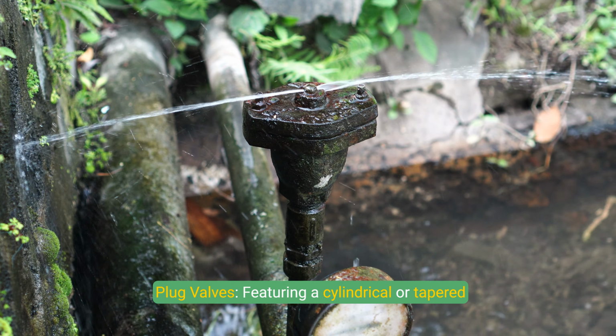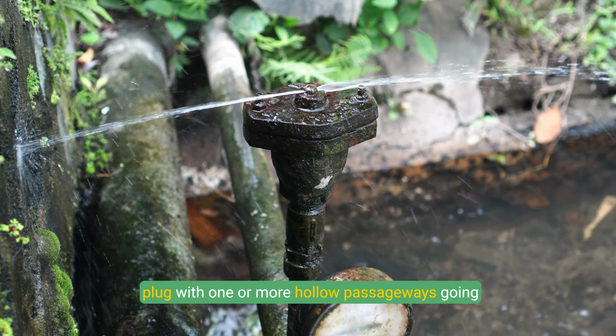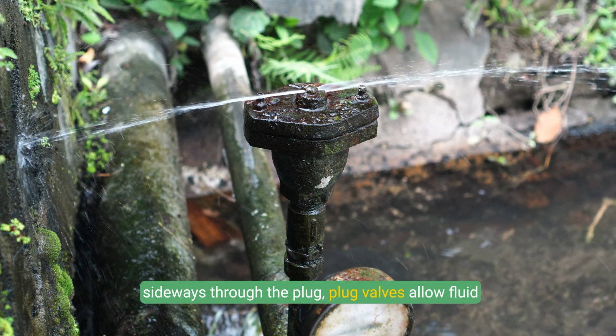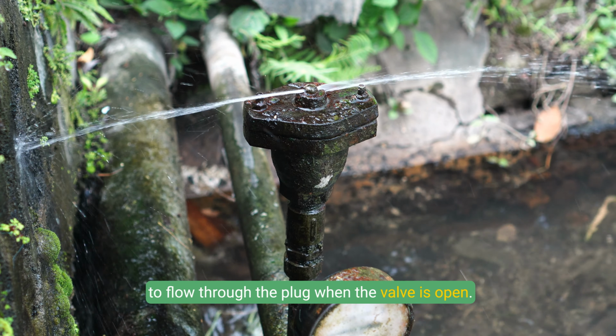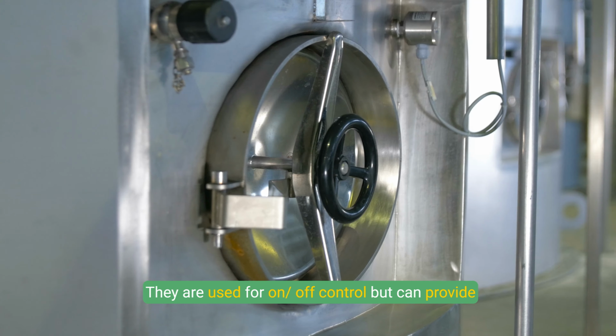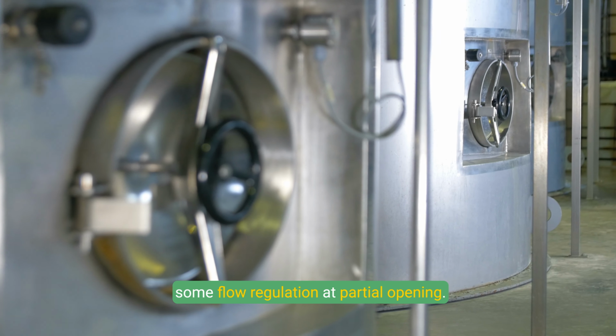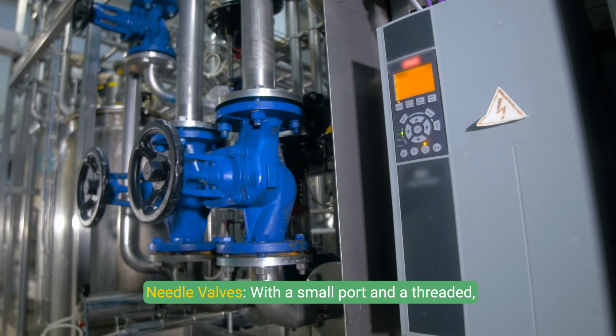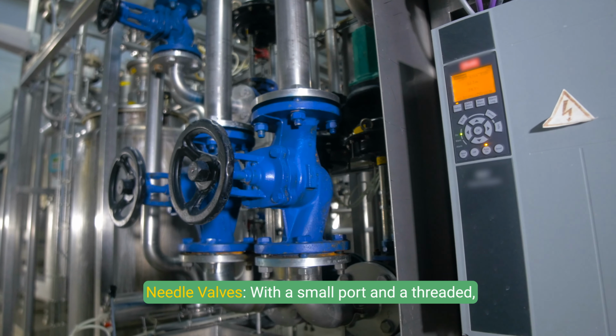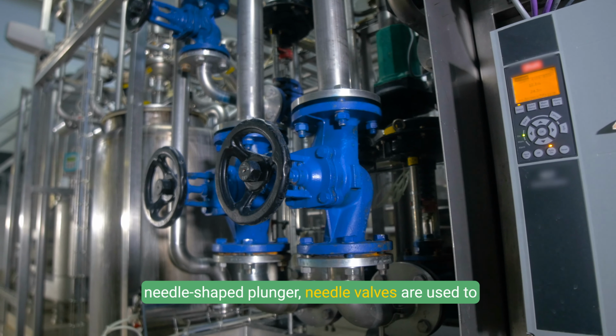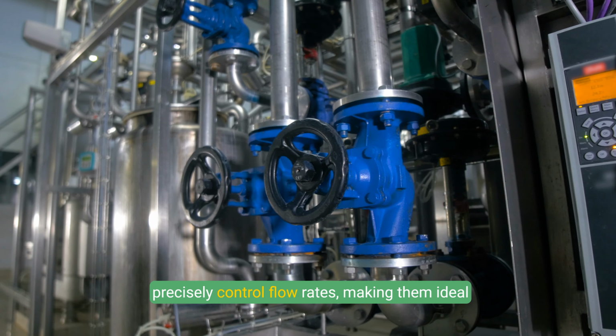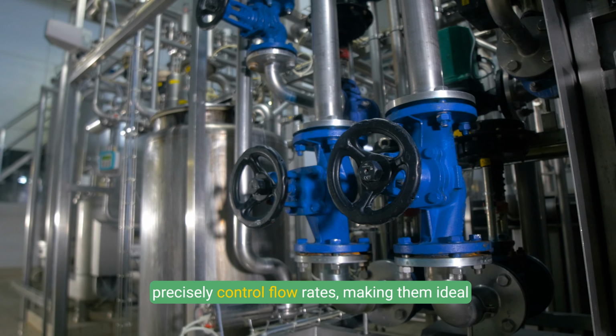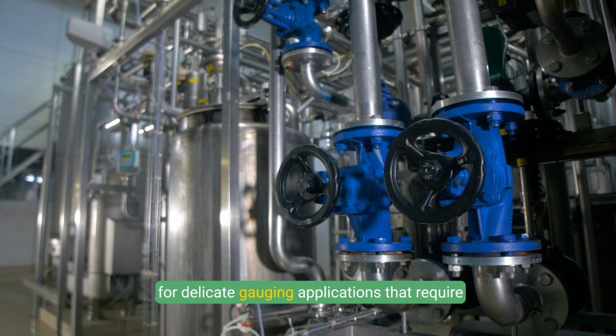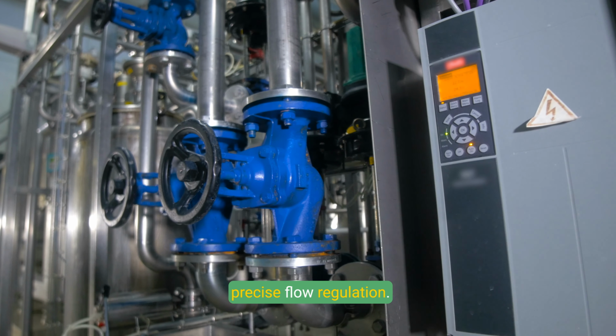Plug valves. Featuring a cylindrical or tapered plug with one or more hollow passageways going sideways through the plug, plug valves allow fluid to flow through the plug when the valve is open. They are used for on-off control, but can provide some flow regulation at partial opening. Needle valves. With a small port and a threaded, needle-shaped plunger, needle valves are used to precisely control flow rates, making them ideal for delicate gauging applications that require precise flow regulation.